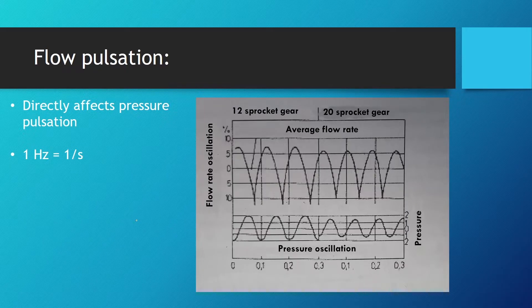Now let's talk about something really important: pulsation of flow. Because of the periodical extrusion of fluid from the gear pump, we have flow pulsation. Flow pulsation is directly responsible for pressure pulsation as well, and pulsation makes noise. It is not something we can eliminate — it is always present at some level. Some pumps have lower levels of pulsation than others.